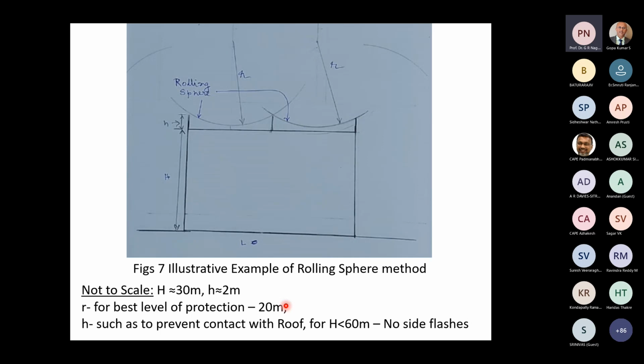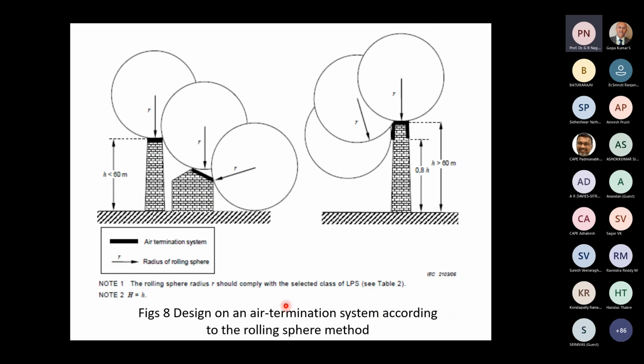We have seen this figure already. Height is less than 60 meters, no side flashes. Now this is a photograph reproduced from IEC standards 62305 part 3. Here you'll see that if the height is less than 60 meters, the sphere is rolled on the top surface. The rolling sphere is rolled only on the top surface. So we'll see that this will contact the top surface entirely for this building, but it will contact only one side of this sloping roof here, and then subsequently it contacts only the ground.